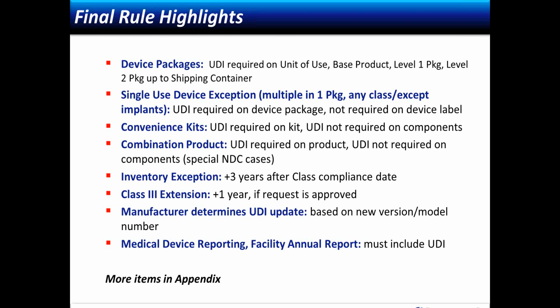I suspect then I know the answer to Irene's question, which is if I have a primary, secondary, and tertiary bit of packaging for a product, and all of these packages have labels, do I have to place the UDI at the package and the label, or can I just update the label and keep the package as it is? So this is pretty clear in the final rule that the UDI must appear both on the device label and the package, and also applicable to each package level. So as you go up from the primary, secondary, and onward, each of those package levels would need to have their independent UDI value. Okay.